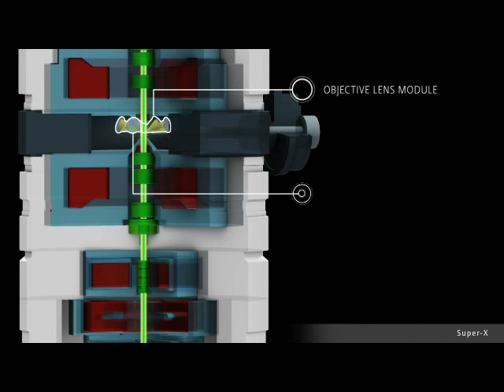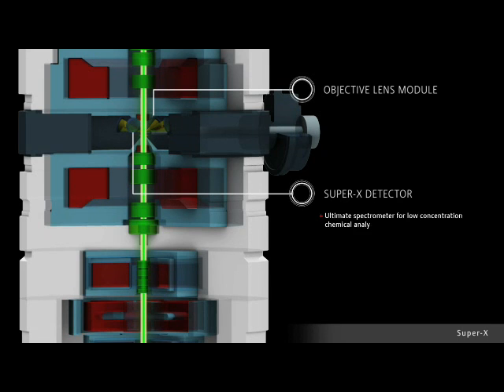This powerful combination of unique technologies in one platform is now complemented with the ultimate spectrometer for low-concentration chemical analysis, atomic resolution chemical mapping, and 3D chemical mapping, the SUPER-X detector, which is part of the FEI patented ChemiSTEM technology. The symmetric design of four detectors around the sample increases the collection efficiency and allows for flexibility in tilt without losing the EDS signal.